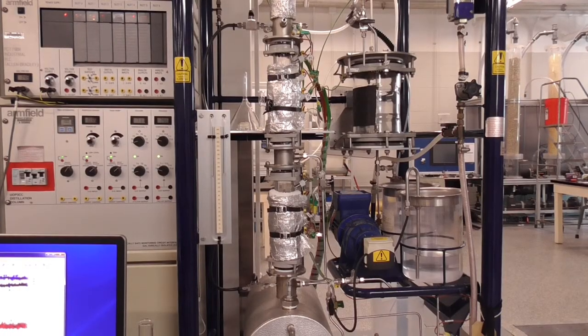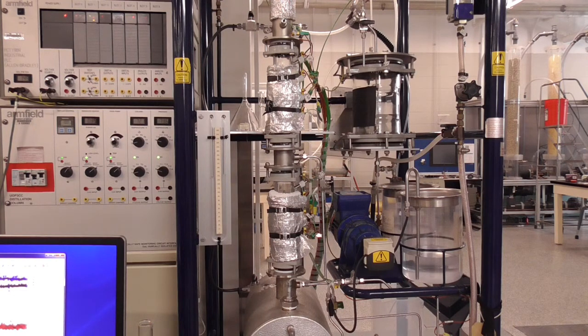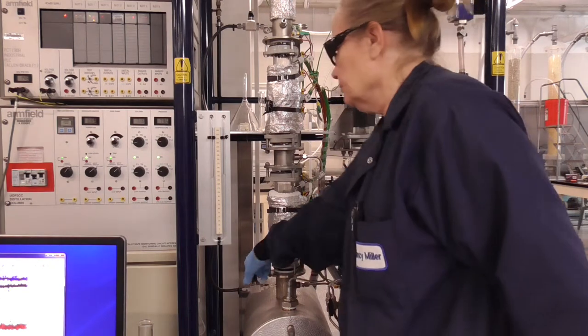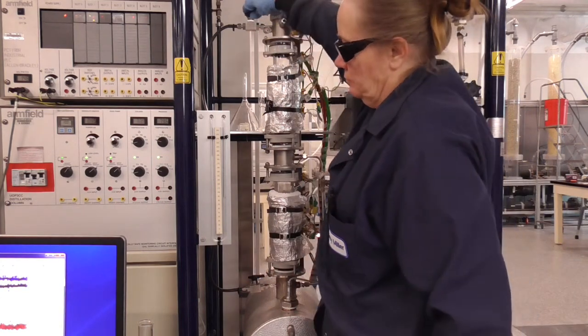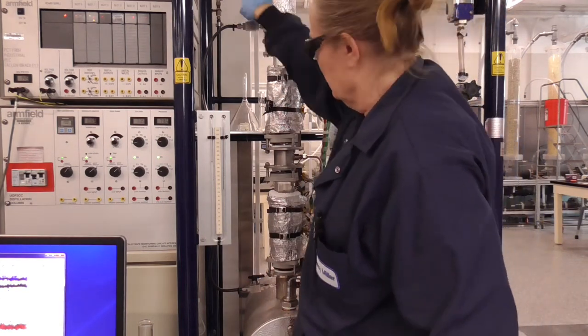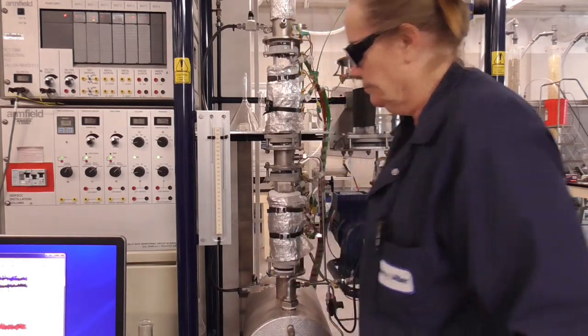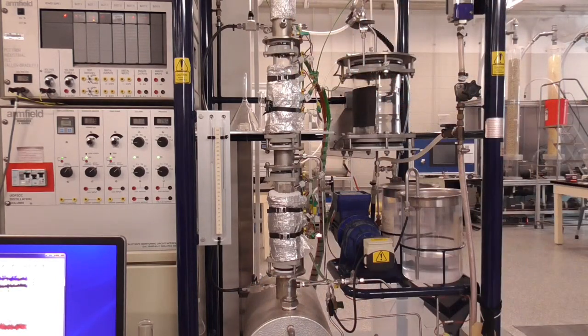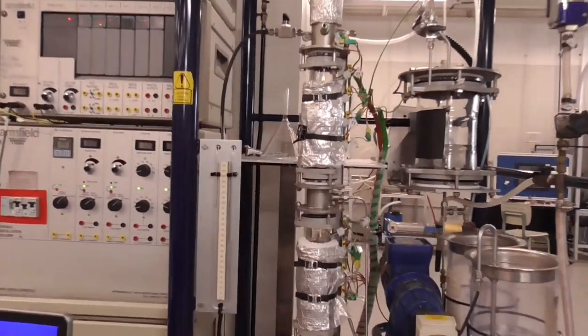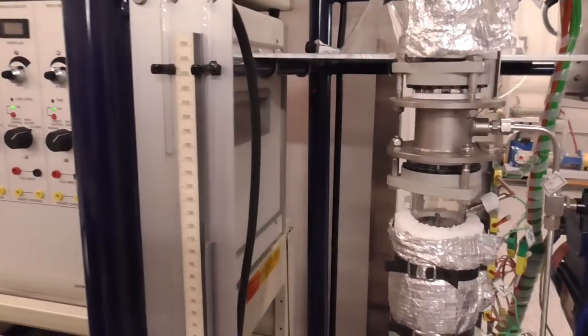In order to measure the pressure, I'm going to open V6 and V7, and the pressure will go into the manometer, and then I will close the valves. The pressure stays in the manometer, but we close the valves so that vapor does not back up into the water. And we can now read the manometer in centimeters of water.